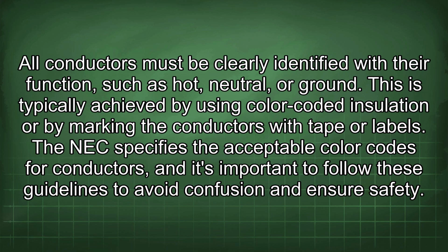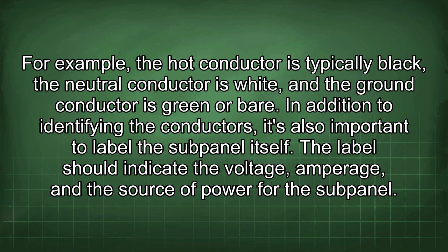All conductors must be clearly identified with their function, such as hot, neutral, or ground. This is typically achieved by using color-coded insulation or by marking the conductors with tape or labels. The NEC specifies the acceptable color codes for conductors, and it's important to follow these guidelines to avoid confusion and ensure safety. For example, the hot conductor is typically black, the neutral conductor is white, and the ground conductor is green or bare. In addition to identifying the conductors, it's also important to label the subpanel itself.